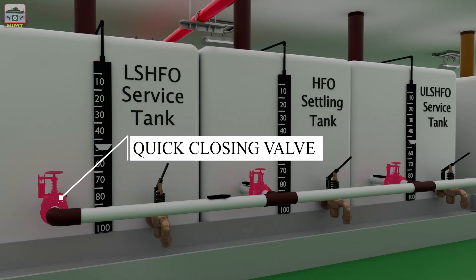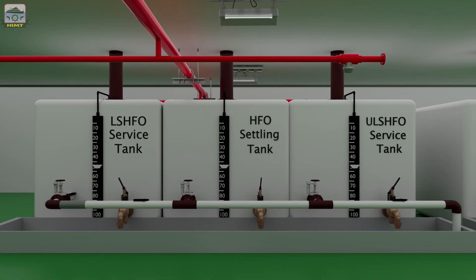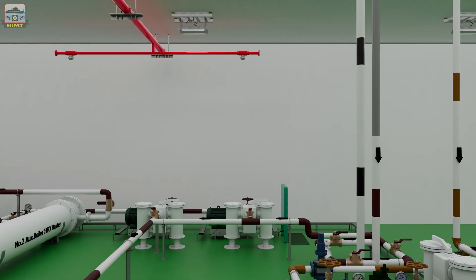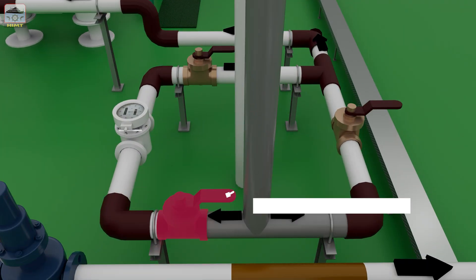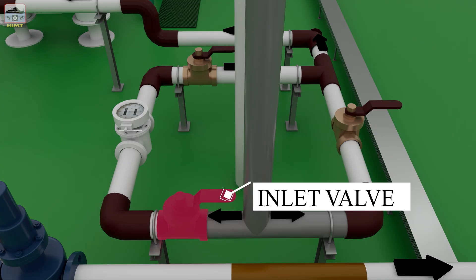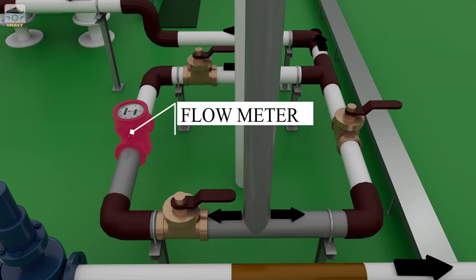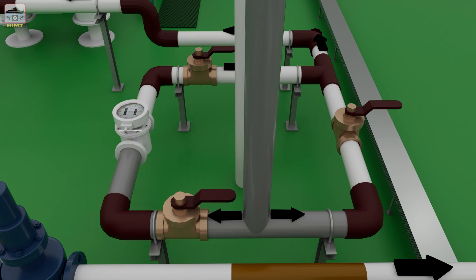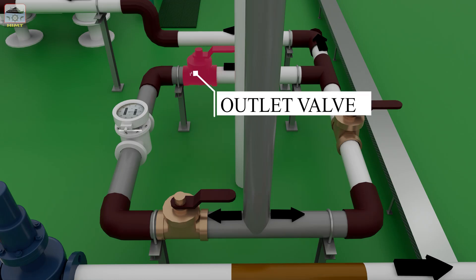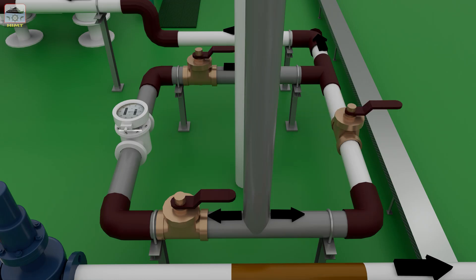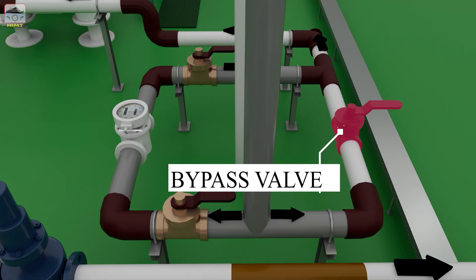Quick closing valves, which can be closed from outside the machinery space in case of fire inside the engine room. Inlet valve to the flow meter. Flow meter — this is used for the calculation of heavy fuel oil consumption for the boiler. Outlet valve of the flow meter. Bypass valve for the flow meter.